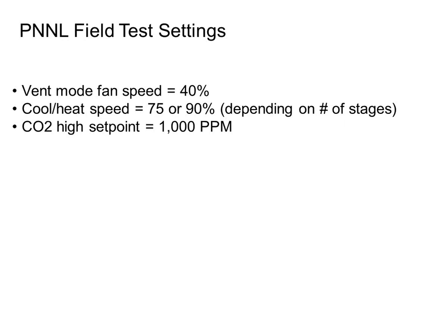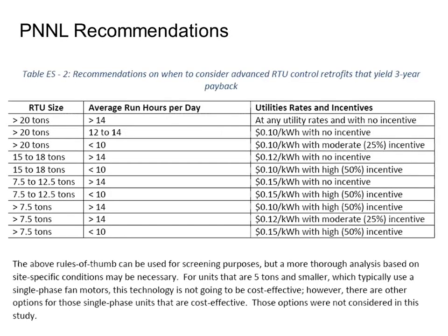They had a CO2 set point of 1,000 parts per million, which is kind of conservative. They could certainly get more aggressive than that, and we'll talk about that today. But that's what they chose for this particular study. So this was kind of the summary, if you will. And like I said, there's a 300-page study. You can read it all.